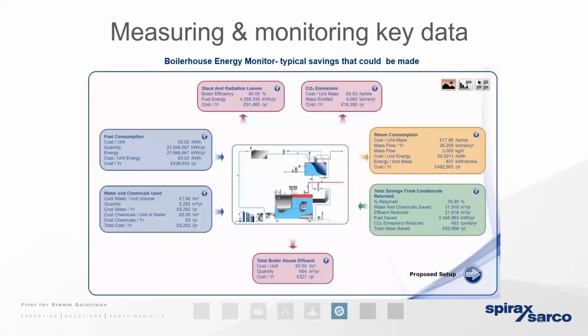Now we can take that one step further, because all of our area engineers have got detailed software on site. So if we know a few key parameters on a steam using site, for example the cost of water, the cost of water treatment chemicals, the cost of gas, all of which should be readily available, together with the steaming hours, then we can determine all of the variables that you can see on the screen. We can determine the financial value of condensate. We can tell them how much condensate is being recovered. We can then compare that to how much should be recovered and identify white space for cost-saving analysis.